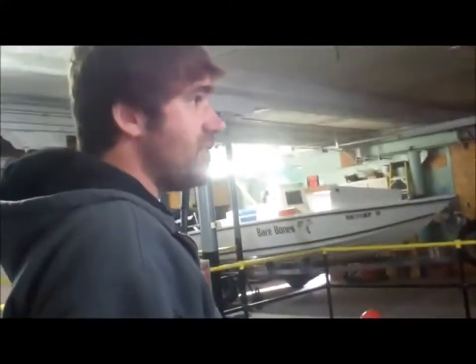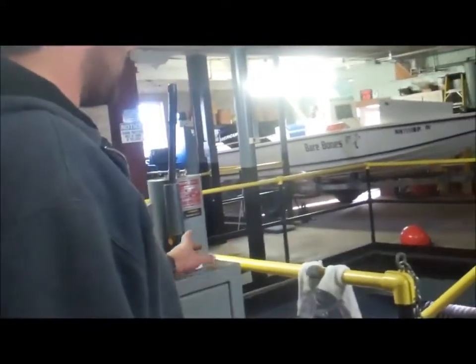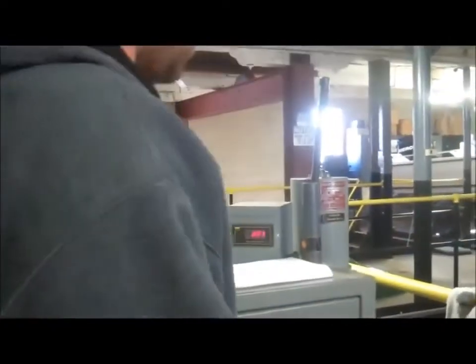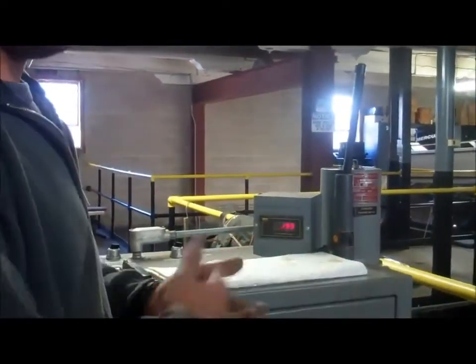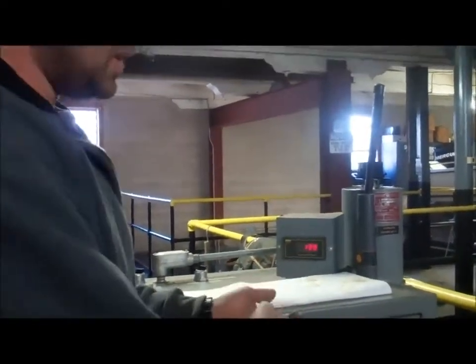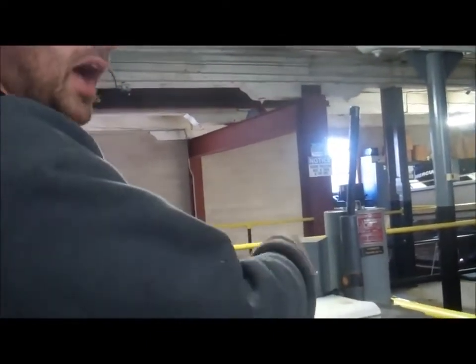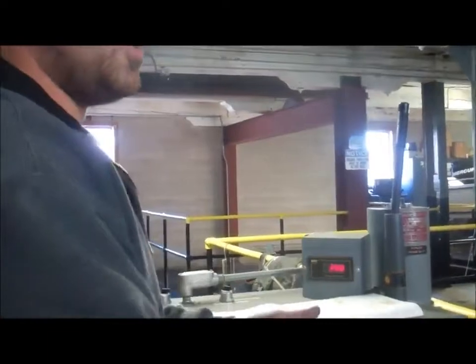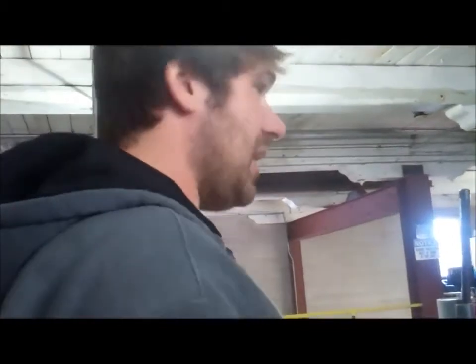This is our accumulators. This is how we shut down. Every machine has one of these. They look different, but they all function about the same. This is a nitrogen pressurized tank, and we keep about 1,200 psi of pressure. It's got nitrogen with hydraulic fluid on the bottom of it. When we shut down or we lose power, there's an electric solenoid that opens and releases that hydraulic pressure to hydraulically shut down these machines. So you don't need power to shut down. That's the whole idea behind it. And if you didn't shut them down, they would just go faster and faster until they blew themselves apart.